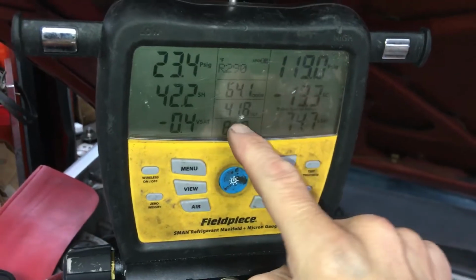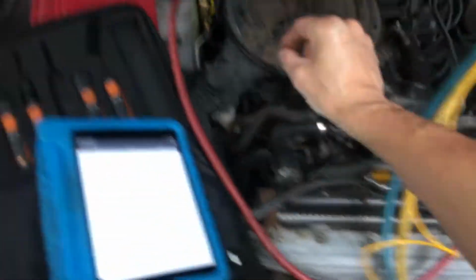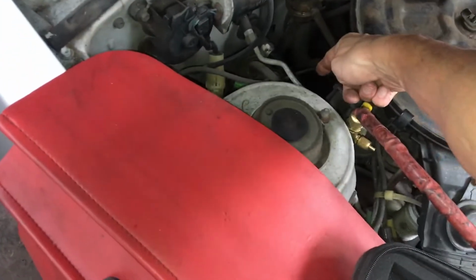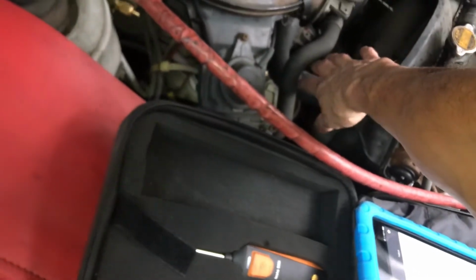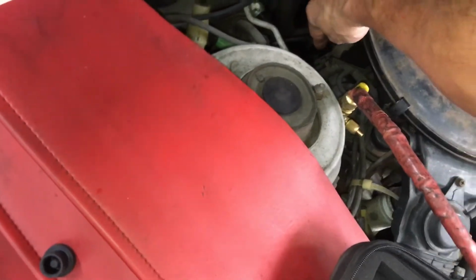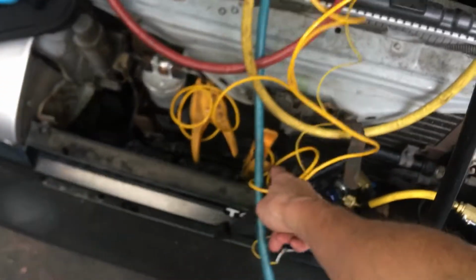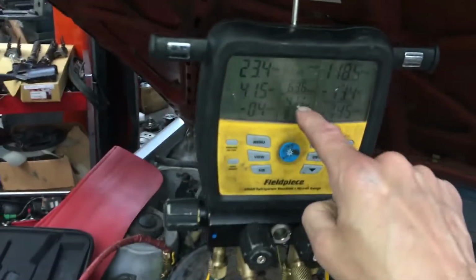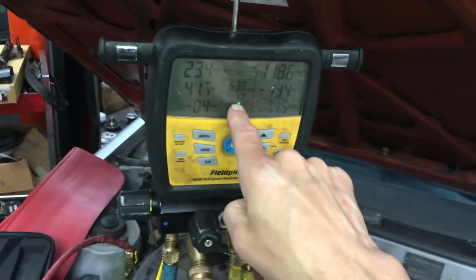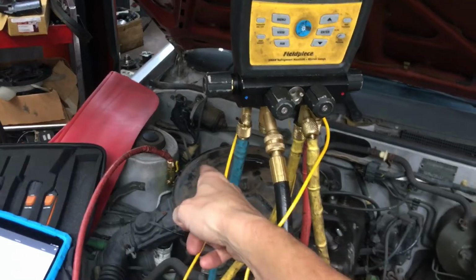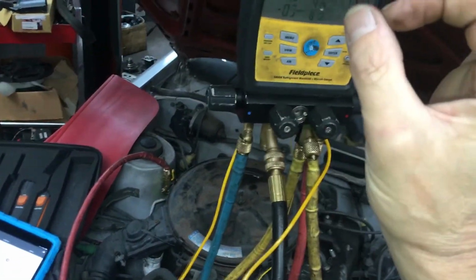So here's our suction line temperature. I'm taking it at this point because when I put my suction line temperature clamp over here, I have convection heat from this hot air that's like 140, 160 degrees blowing over my probe right here. And I have the exhaust manifold direct radiant heat onto my probe. So when my probe is attached over there, the suction line temperature is 57 degrees. It's not 57 degrees. That's the radiant heat and the convection heat that is affecting my probe.